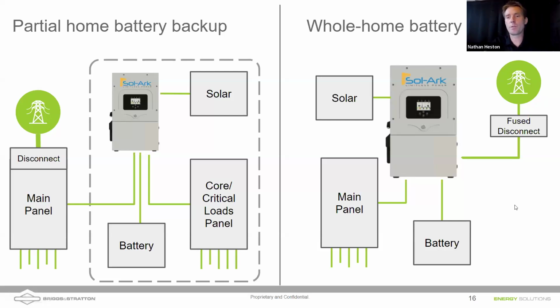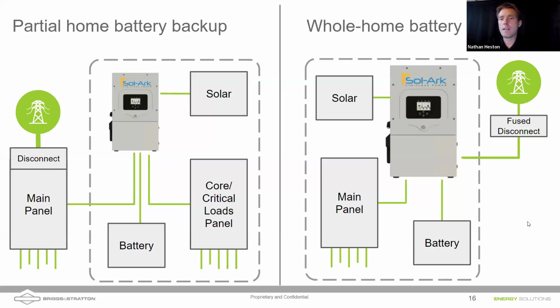The difference here on the right side of the screen, we're showing a Sol-Ark 15K. You are connected to the grid through a 200 amp disconnect. And then in a grid down situation, all of that power from the batteries or potentially from the solar as well can flow into the main panel of the house and back up all of the loads, while still not exporting anything to grid, protecting those linemen that might be out there working on repairing the lines. Notice we are not having to install an additional loads panel in the house and move loads over.